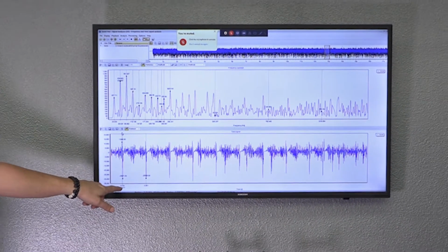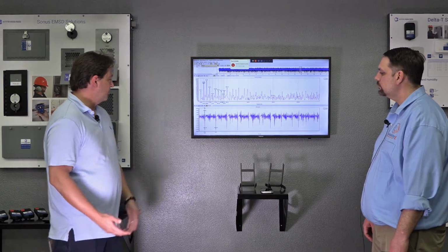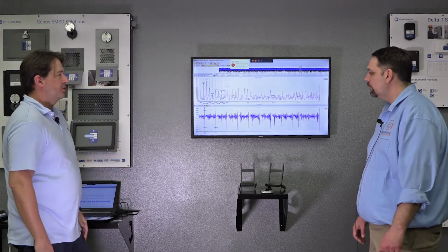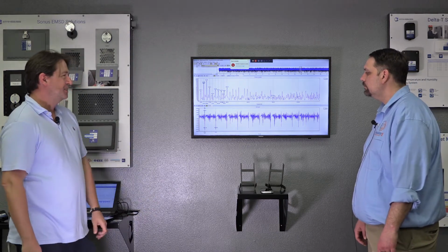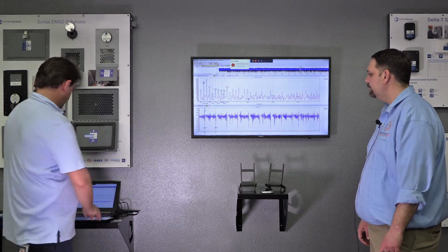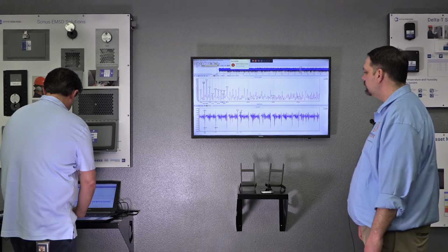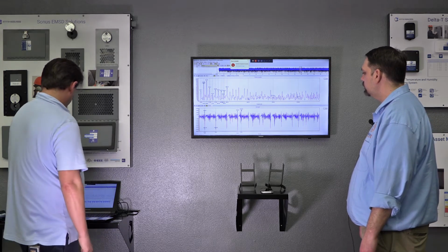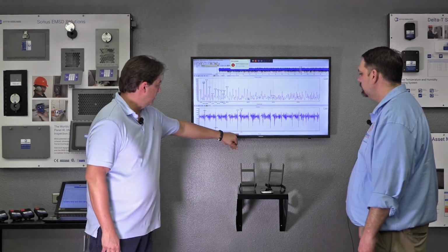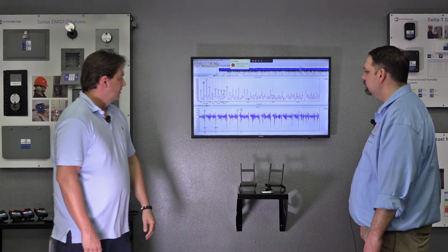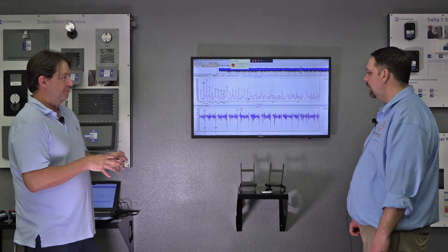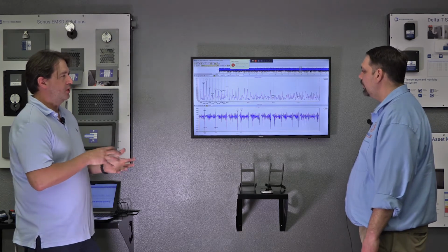Again, we can start calculating our distance between these peaks, and we're starting off at 0.016 to 0.051. So you can do the math real quick and figure, hey, am I at a 0.016 value? Off the top of your head, not quite there, right? We're a little beyond. So let's take a look at some of these other ones. If we go from this one, right there, 0.118 to 0.129, still not quite there. So we know we don't have an electrical fault going on, because we're not seeing a 60 hertz or a two-times event at 0.008.